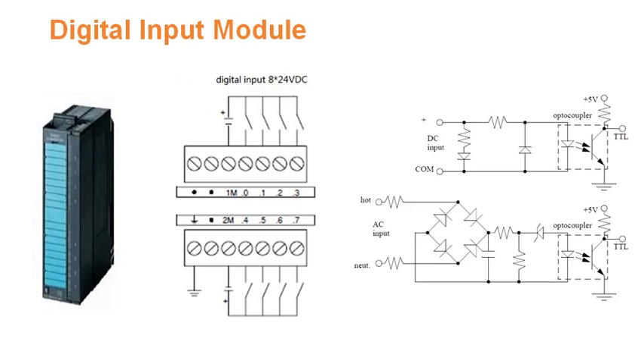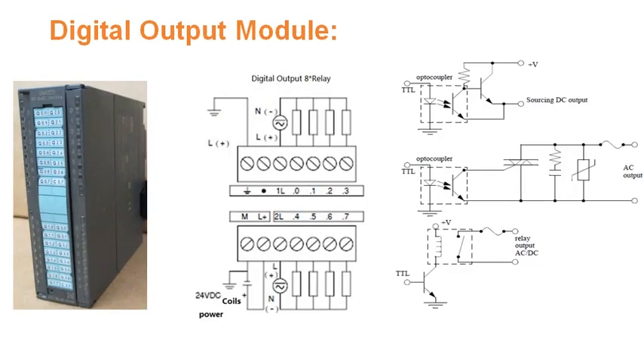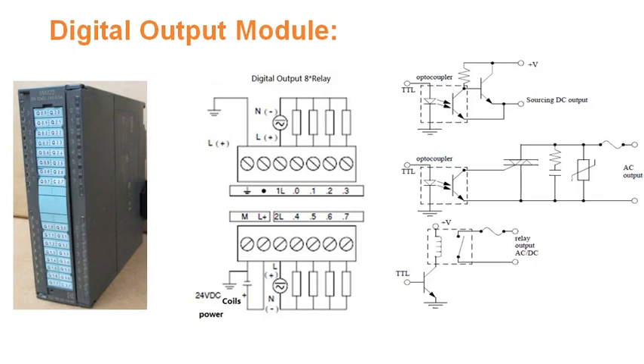The digital output module shown here is of relay output module. The advantage of relay output module is we can connect either AC or DC controlling devices. But disadvantage of this relay output module is you cannot use for fast switching applications. If your application requires fast switching, then you can go for opto transistor for DC control devices and opto triac for AC control devices. Thank you for listening to my lecture.